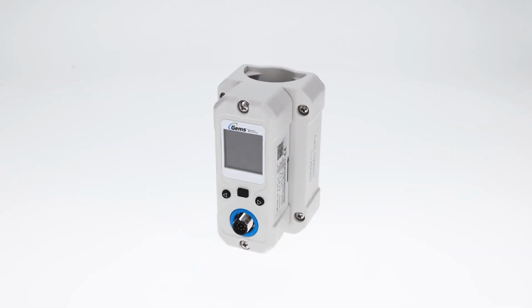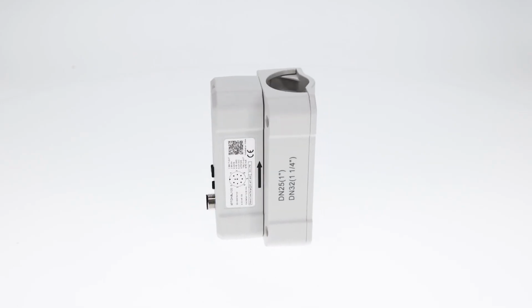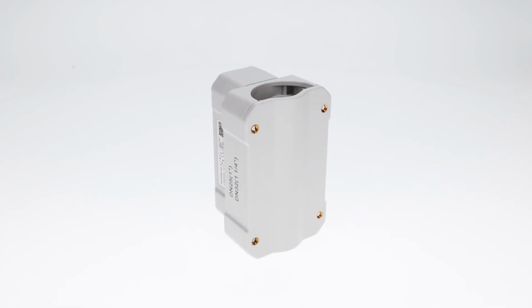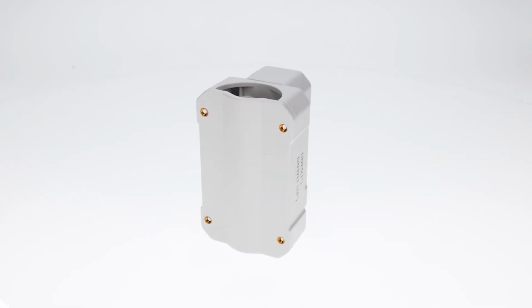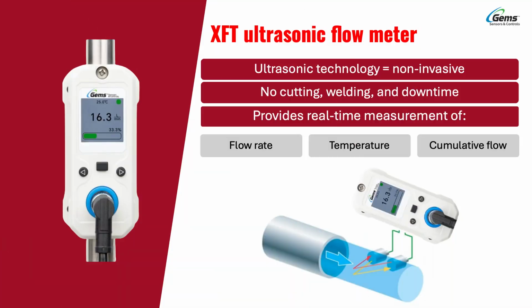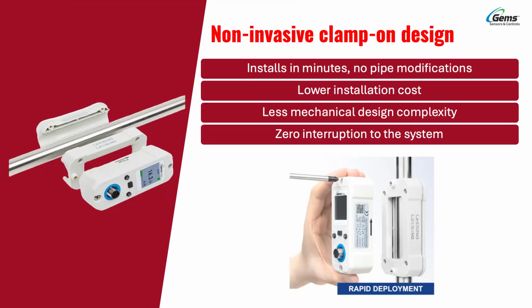The XFT is a clamp-on ultrasonic flow meter that attaches directly to the outside of a pipe. No cutting, no welding, and no system downtime. It provides real-time measurement of flow rate, temperature, and cumulative flow. Because it's completely non-invasive, it avoids contamination risks, eliminates pressure loss, and works with existing hard pipe installations. The XFT installs in minutes using external clamps. No pipe modifications required. That means lower installation costs, less mechanical design complexity, and zero interruptions to the system.